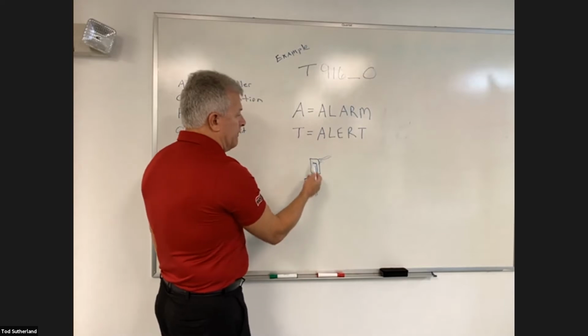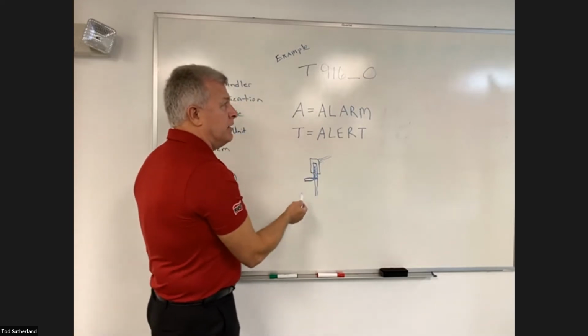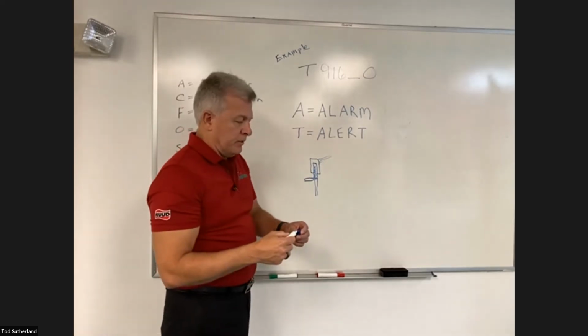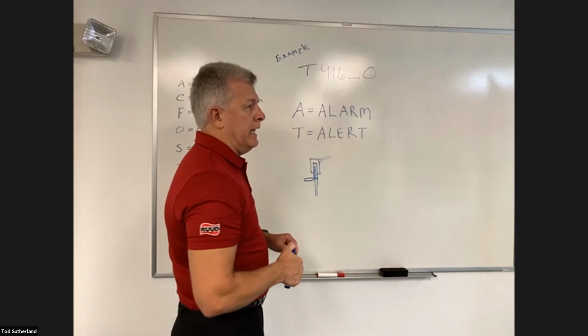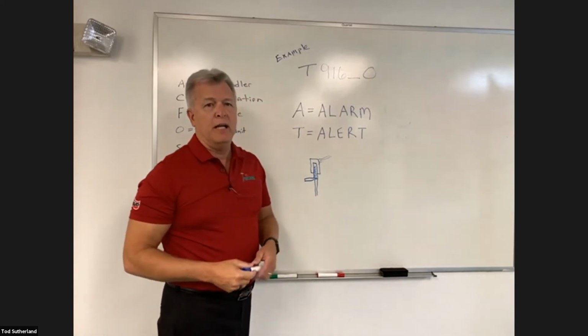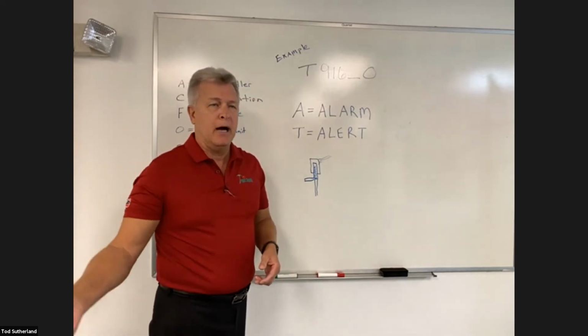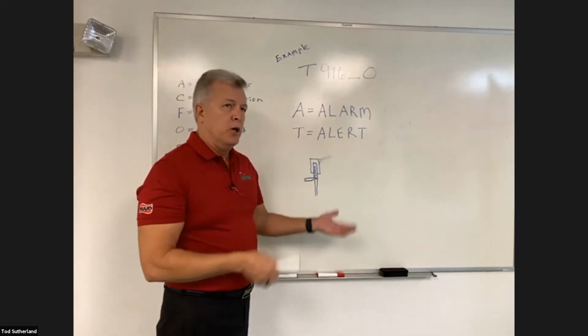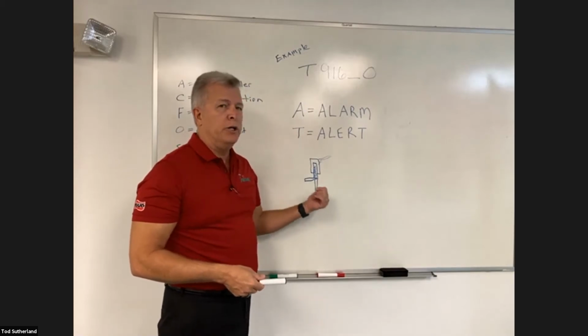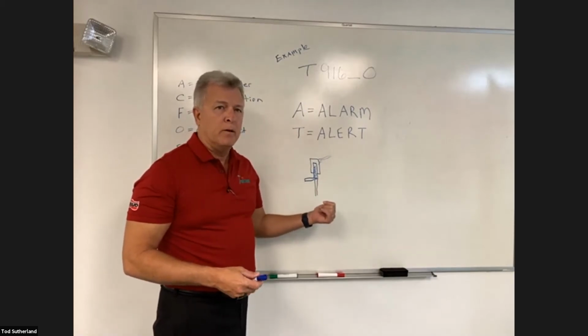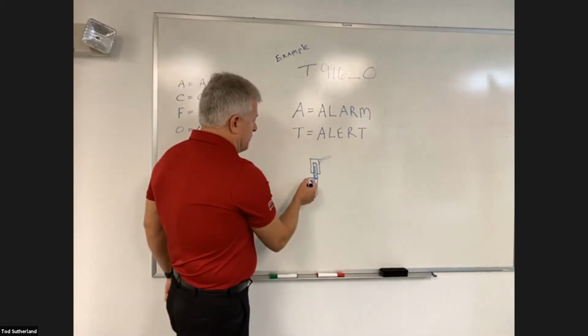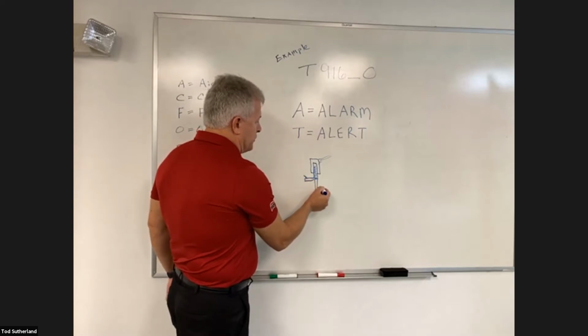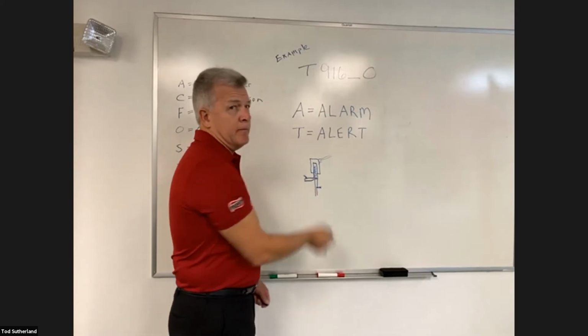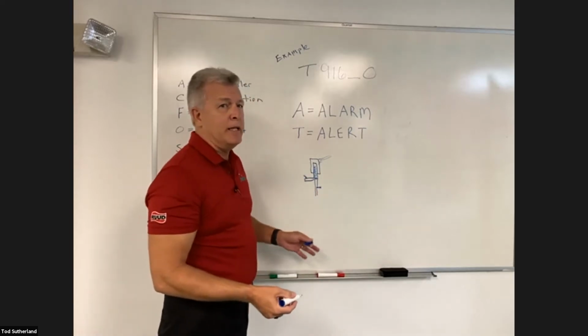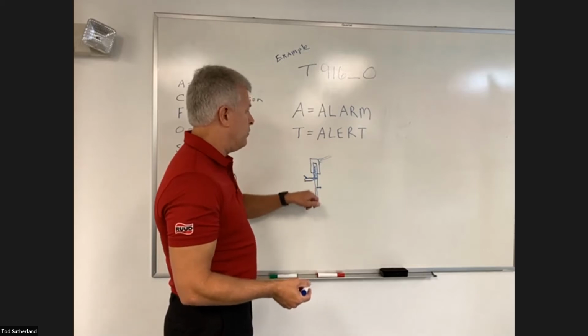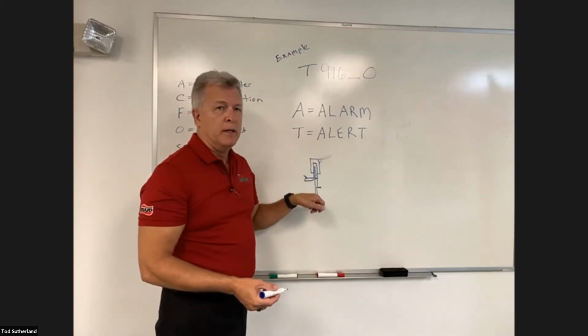So if you're ever having to test this valve, for example, if you're in the cooling mode and you suspect you have a valve failure in the heat pump unit in the outdoor unit, if we're in the cooling mode, the valve in the outdoor unit should be wide open. So if you take a temperature reading on this and a temperature reading here, they should be the same. If they're not the same, then you either have a restriction in the valve or your valve is partially closed.